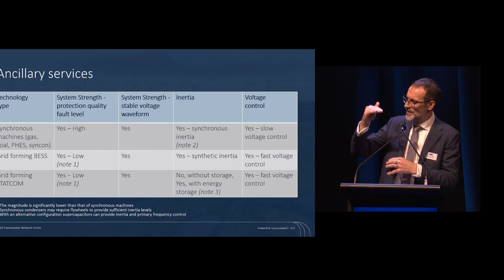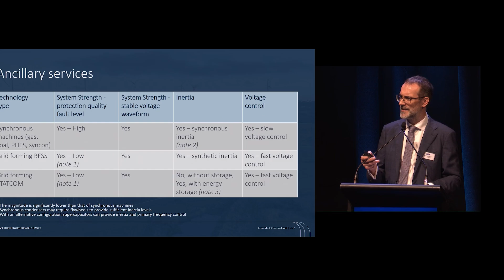That's what these ancillary services do. They can be provided by coal power stations, gas generators with a clutch, pump hydros running in synchronous condenser mode, and synchronous condensers themselves. Grid-forming batteries can also provide these services, and in Europe they're starting to use grid-forming STATCOMs. So there are a number of opportunities to provide these services.